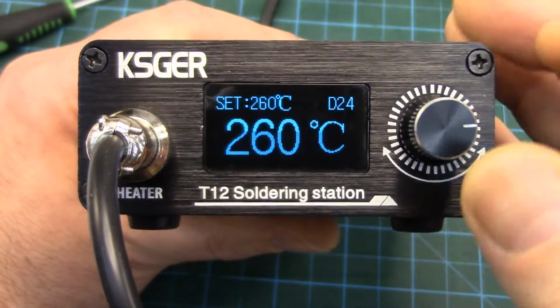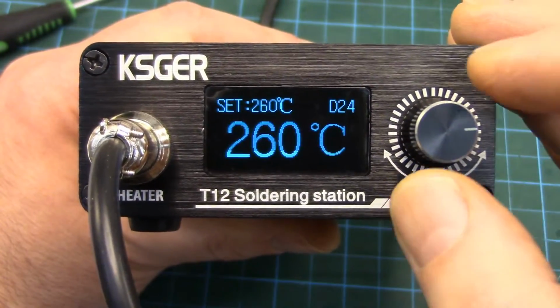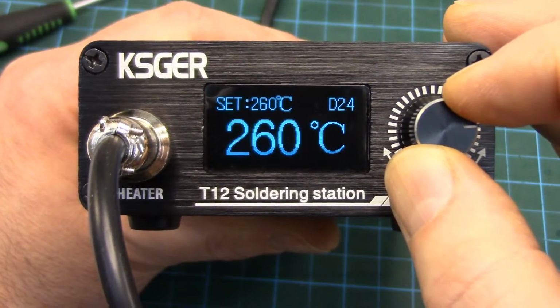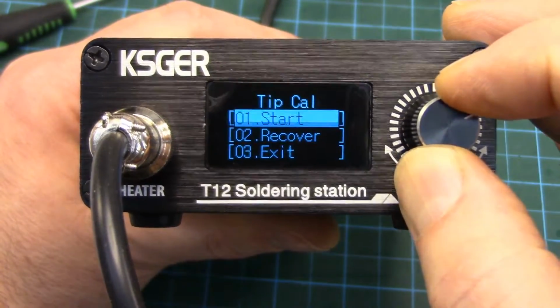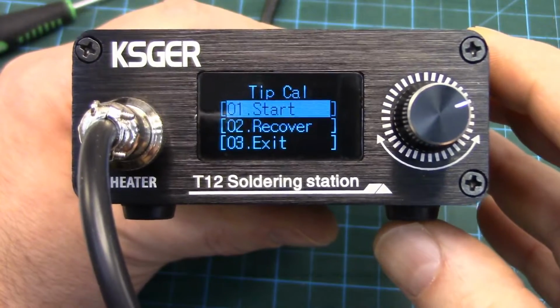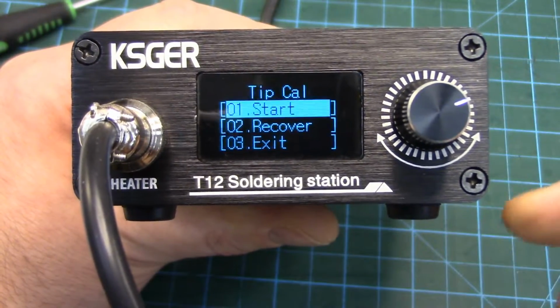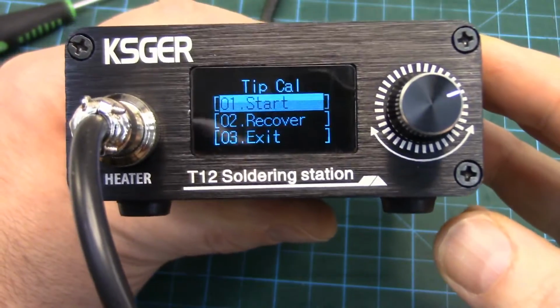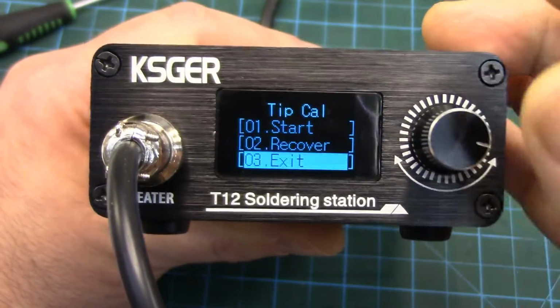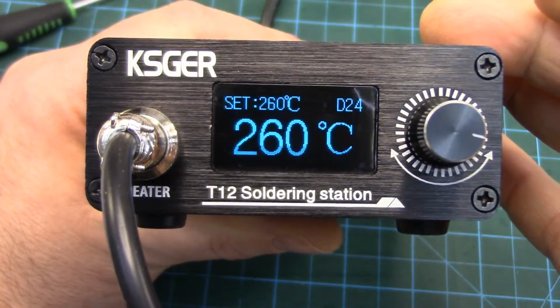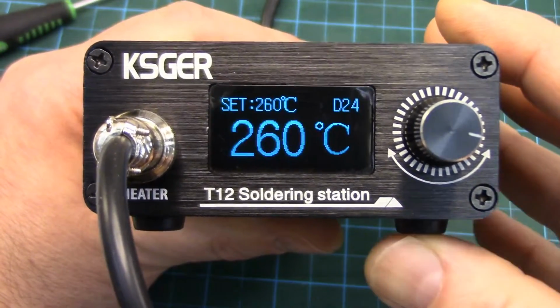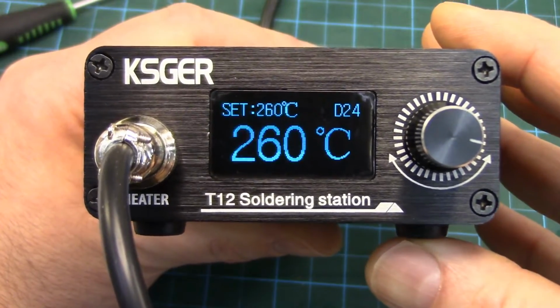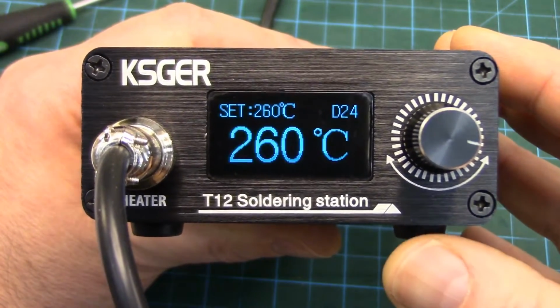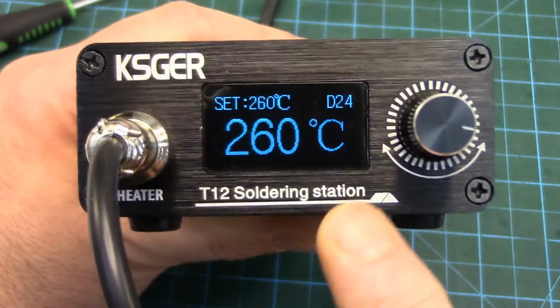And to go into calibration mode, you push in the encoder and turn counterclockwise or left. And there's the tip calibration menu. Again, I've got a separate video on that. I'll link to it below in the description. So now that we've got that all set, let's see how accurate this thing is out of the box before even calibrating a tip.